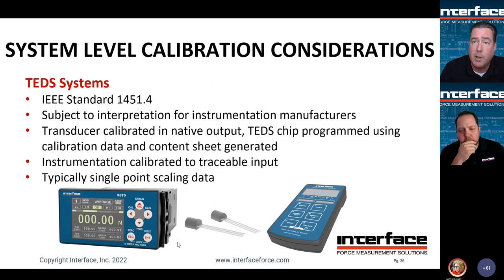So if we provide a load cell with TEDS, we'd want to make sure that the instrument itself has a traceable cert stating how it is interpreting a millivolt per volt input. And typically speaking, these are single point scaling data type devices. There are some different templates that address the calibration data slightly differently, but most commonly at interface, it's single point scaling data. Next slide, please.